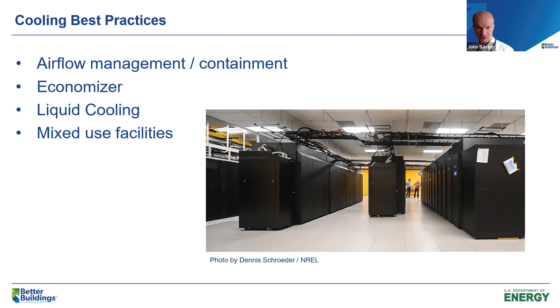The third bullet is liquid cooling. We're starting to see a lot of this on the data center side, mostly a lot of conversations around that, although there are some, especially high performance computing and crypto, that are actively in that liquid cooling space. It allows a lot of opportunities in terms of less fan energy use, both for the facility and the server, plus elevated temperatures. And finally, I'm going to talk a little bit about mixed use facilities.